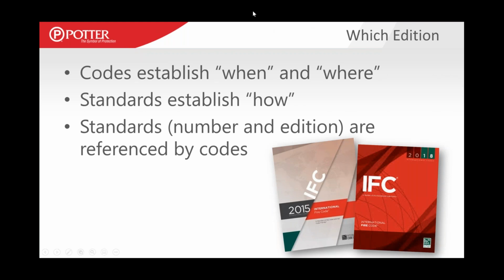NFPA 25 is a standard, of course, a standard for inspection, testing, and maintenance of water-based systems. So the codes establish the when and where. Standards typically establish the how. That's the simplest way to remember it. So the fire code, whichever fire code is adopted, establishes the when and where. It says when you have a sprinkler system, it has to be maintained in accordance with NFPA 25. So the standard establishes all the detailed rules for how to perform those inspections and tests.